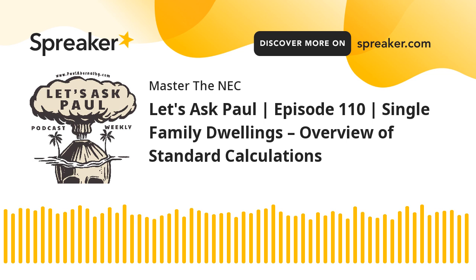Now, in the 2020, it goes on for another paragraph. It says, where a motor is part of the non-coincident load that is not the larger of the non-coincident loads, 125% of the motor load shall be used in calculating if it is the largest motor. Okay, so what does that mean for a single family dwelling? The first step you should always do is if you have non-coincident loads, let's just say it's heat versus AC, compare the heat versus the AC.